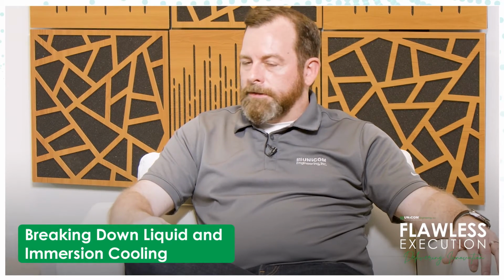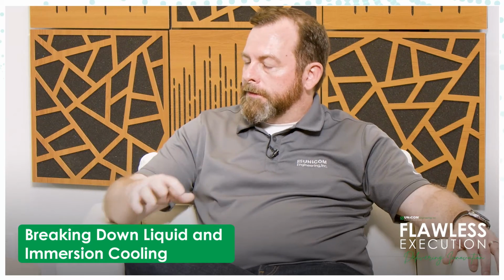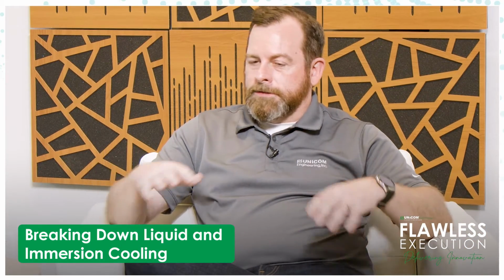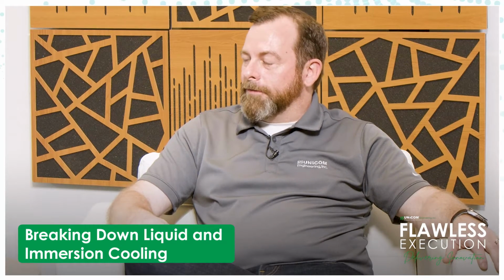If you're using traditional racks, you still usually need some type of water cooling loop, some type of heat exchanger to go through. Same thing in data centers that are looking at moving to immersion. If you already have that water loop in place going to chillers, you're a good chunk of the way there. It's just making sure your floors can support the extra weight, which is nice for a lot of places. You can go right down on a concrete slab as opposed to having to have a raised floor and things like that.